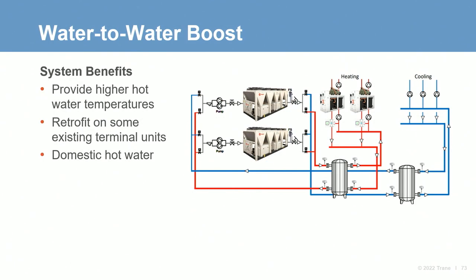Now, as Charlie mentioned earlier, in some applications, terminal units still require 180 degree Fahrenheit water, even after transitioning to heat pump technology. And typical air-to-water heat pumps are limited to about 140 degrees Fahrenheit. In these cases, water-to-water units can be used to boost the supply water temperature to the terminal units. System controls need to ensure the source and supply loads are balanced or fighting will occur.